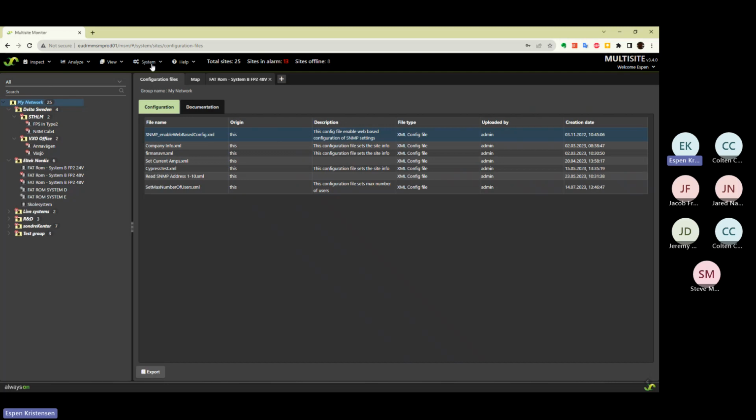Or if you have an SNMP enabled system that sends traps from the controllers, you can set up a northbound SNMP system that will take the traps you define as important from the controllers and forward those into a top level monitoring system. A lot of our telecom customers have those kinds of setups. So this would send it to our NMS system, and our NMS system would handle it from there? Yep.